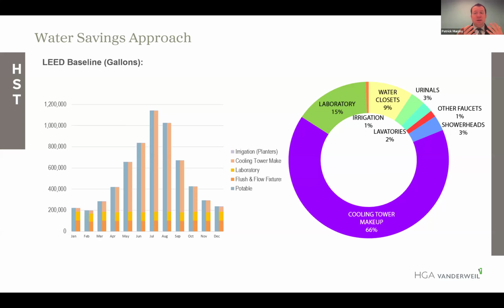But the rest of the loads, what's readily apparent is that it's the cooling tower that is the biggest water use. And we always focus on process water use, or we focus on our plumbing fixtures or things like that, which are important. And I'm really glad to hear the conversation today up until that point. But really, the cooling tower is this opportunity where the energy and water come together and have this dramatic impact. A cooling tower works by evaporating water into the atmosphere to cool it down, and that's part of your cooling system for the building. But there are other ways to cool a building without using any water at all. And also, we can take approaches that reduce the cooling load in the building in the first place, so we don't have to evaporate as much water when we are using those systems. So that was the approach that we took.